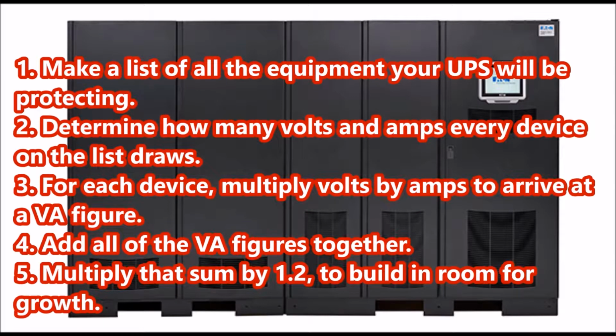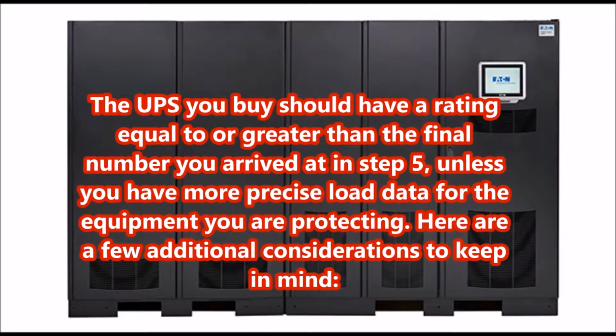1. Make a list of all the equipment your UPS will be protecting. 2. Determine how many volts and amps every device on the list draws. 3. For each device, multiply volts by amps to arrive at a VA figure. 4. Add all of the VA figures together. 5. Multiply that sum by 1.2 to build in room for growth. The UPS you buy should have a rating equal to or greater than the final number you arrived at in step 5, unless you have more precise load data for the equipment you are protecting.